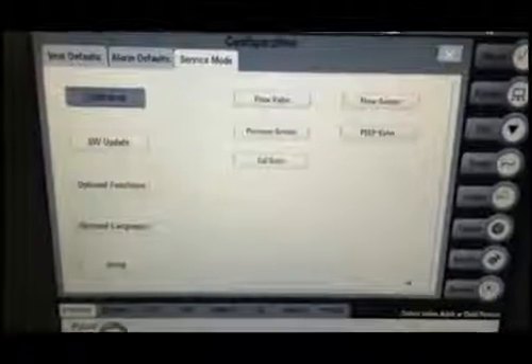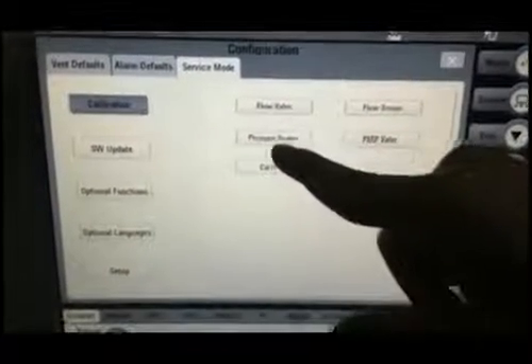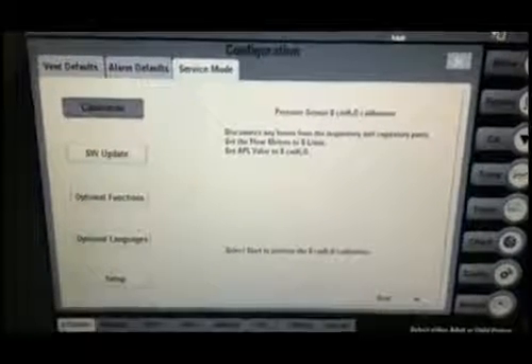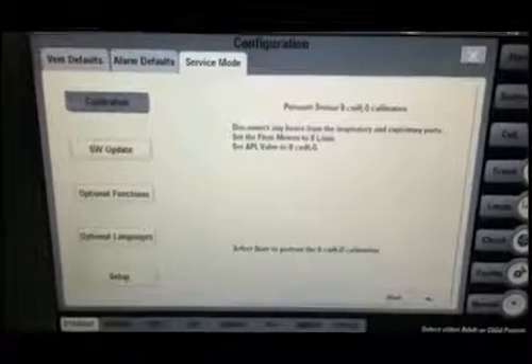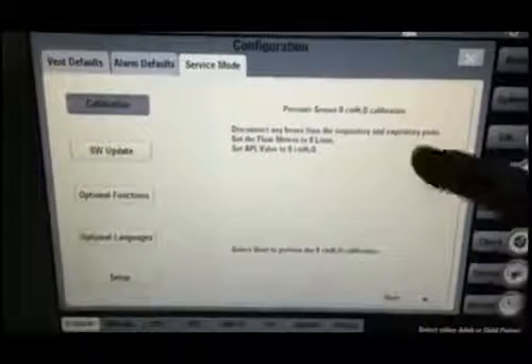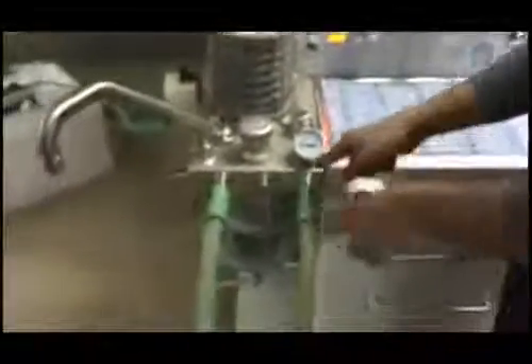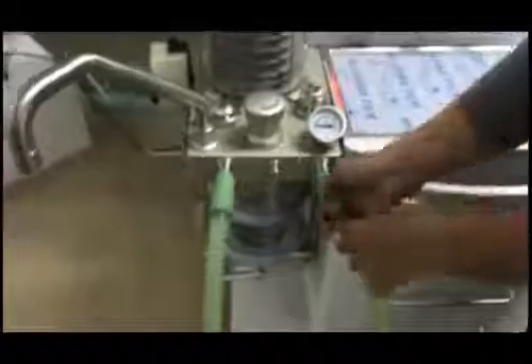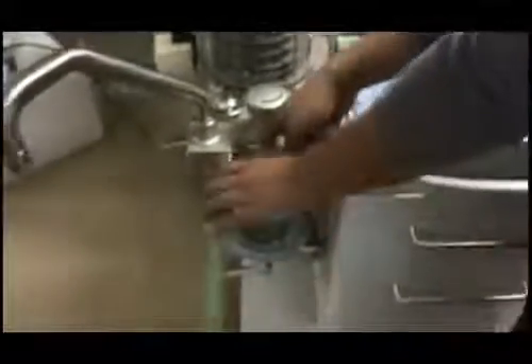We will perform the pressure sensor calibration. In order to perform the pressure sensor calibration, please press the pressure sensor button. Now please read the instructions on the screen. This calibration is to determine the zero of the pressure sensor. The first step is to disconnect any hoses from the inspiration and expiration ports. This is the inspiration port. This is the expiration port.